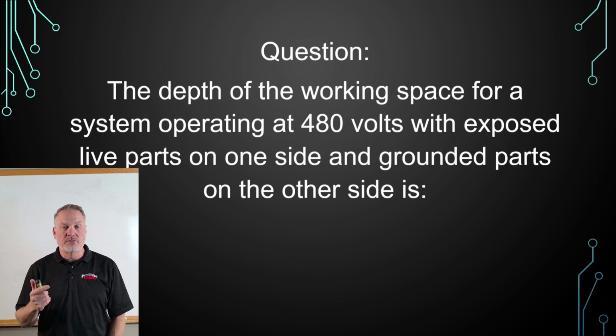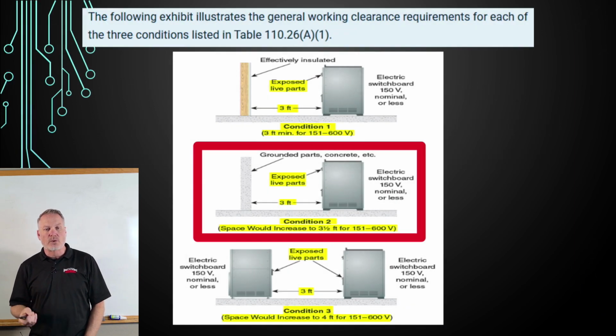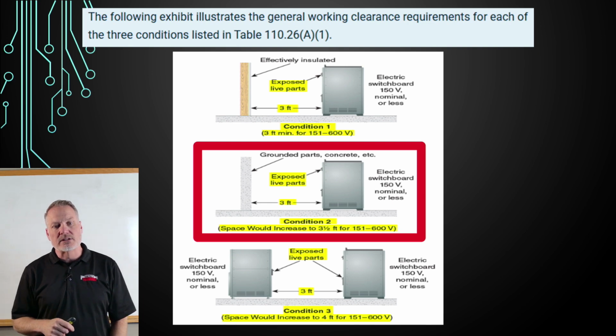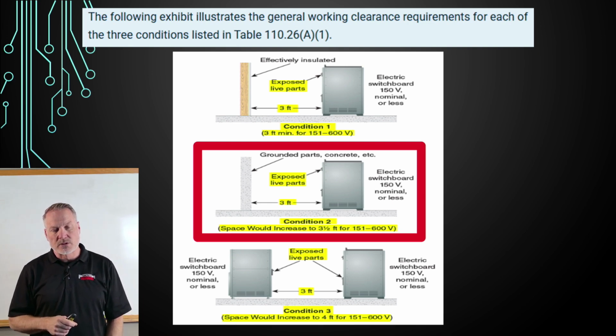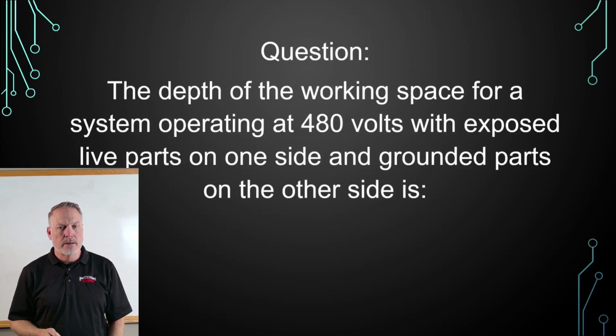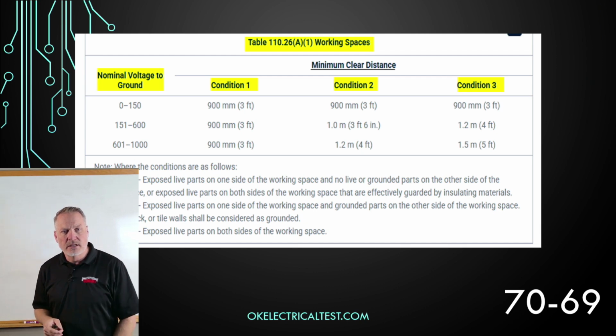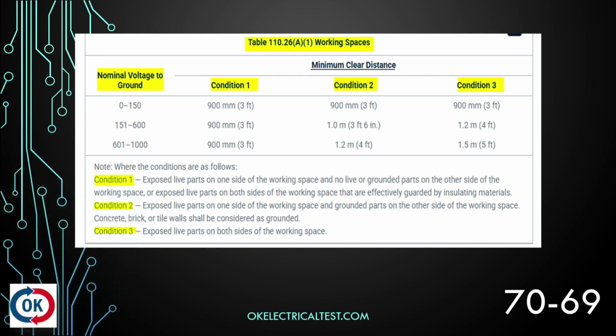For our minimum depth, the first thing to look at is that I've got 480 volts. The second is that we've got live parts on one side of the working space and grounded parts on the other side, and that would be condition 2. So 480 volts, condition 2. Now we take that information to the table and flip back a couple of slides. That takes us down to the second row, 151 to 600, which covers 480 volts. Then we go over to condition 2, and that depth is going to be 3 foot 6 inches deep. So that's the minimum clear distance we have for the depth of our working space.